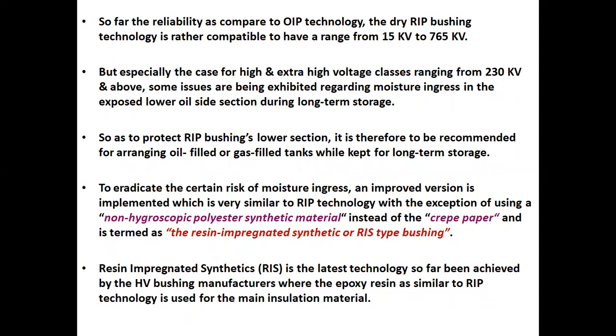So, for reliability as compared to OIP technology, the dry RIP bushing technology is comparable, with a range from 15 kV to 765 kV, but especially for high and extra high voltage classes ranging from 230 kV and above. Some issues have been exhibited regarding moisture ingress in the exposed lower oil side section during long-term storage. So as to protect the RIP bushing's lower section, it is recommended to arrange oil-filled or gas-filled tanks while kept for long-term storage.